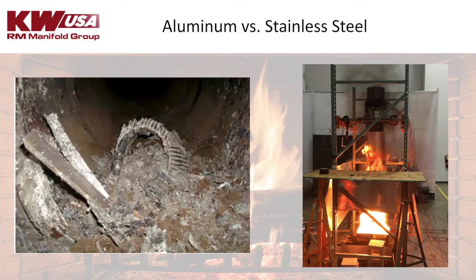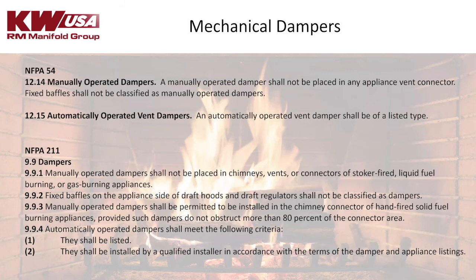It's a great fan. It was actually designed in Europe so that you can turn it off once your flue gets hot and your chimney starts drafting. However, in the U.S., NFPA 211, they're not going to like that. They say to keep your fan running. So you can just turn it down so that once it starts drafting, it's just barely going.